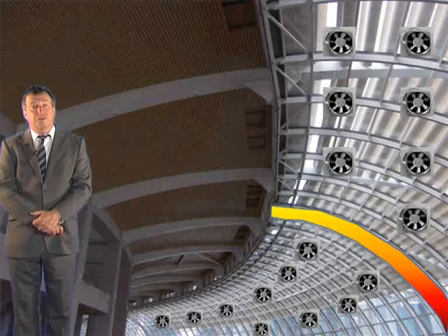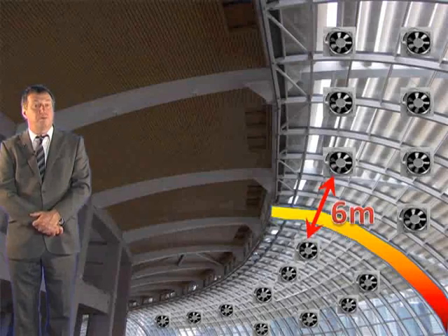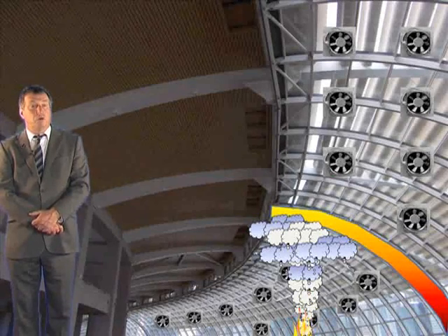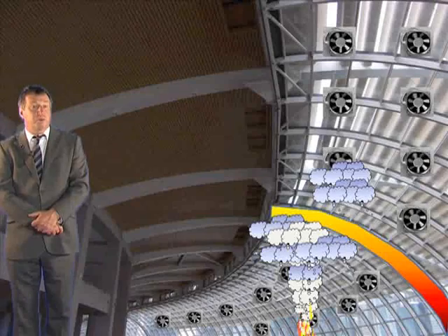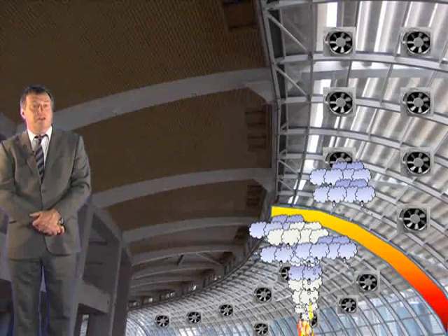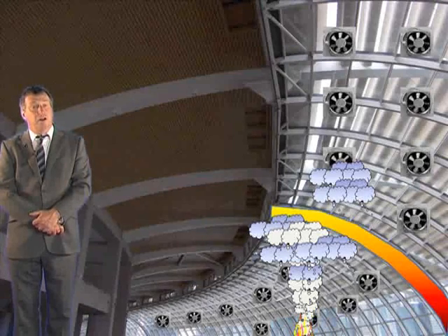Now, before we move on to determining the required sizes or capacities of exhaust points, we must mention the rule for separating ventilators in neighbouring reservoirs. In natural systems, the ventilators in neighbouring reservoirs must not be within 6 metres of each other, as shown here. This is because smoke leaving one reservoir may be drawn into a neighbouring reservoir, thus spreading the smoke around the building. As long as the separation distance exceeds 6 metres, it is deemed very unlikely that smoke leaving the affected reservoir will be drawn back into an unaffected reservoir.